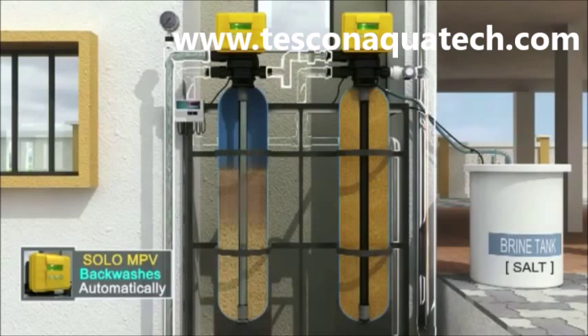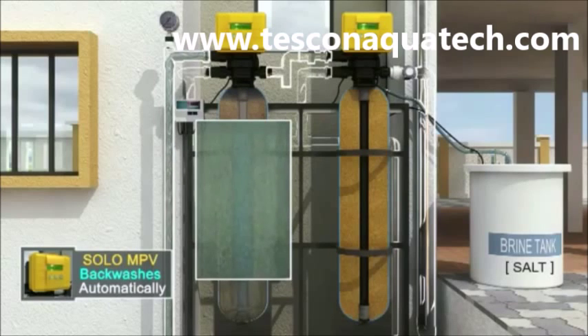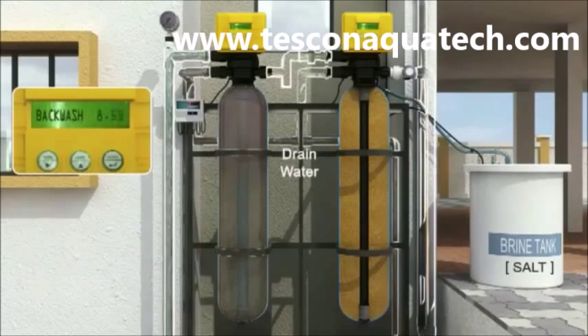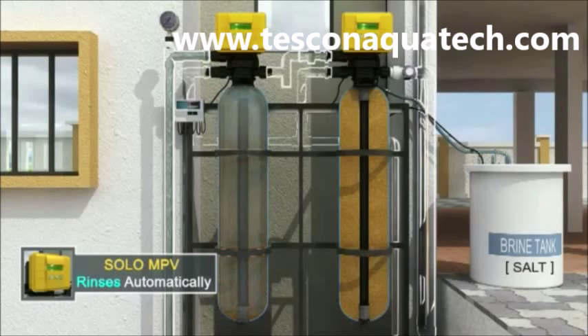Once the programmed volume is counted down, SOLO MPV initiates an automatic backwash of the filter. The reverse water flow makes the sand bed rise and churn so that the accumulated dirt comes out through the drain. The pre-programmed backwash time is counted down during this time.